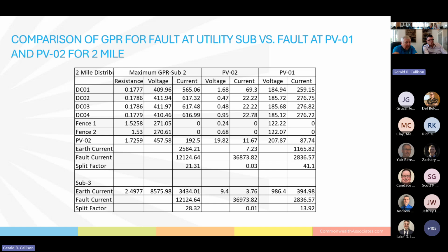But as Gerry described, most of this current is flowing back through the ground grid itself and does not create a ground potential rise. And if you look at what's happening at the fault on the high side of the collector station, fault current is higher and the voltages are higher than they are on the low side, but they are much, much lower than they are for the maximum ground potential rise that happens at the utility substation.